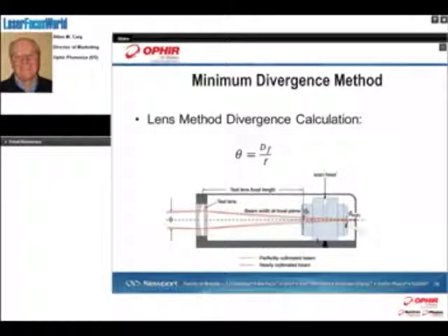So there's a correction factor involved if you're looking at 532 or 632 nanometers, or infrared at 10.6 or 1.06 microns. You will need to make a correction, and there are tables of those corrections, because you want to put this at the exact geometric focus in order to get an accurate measurement of divergence.